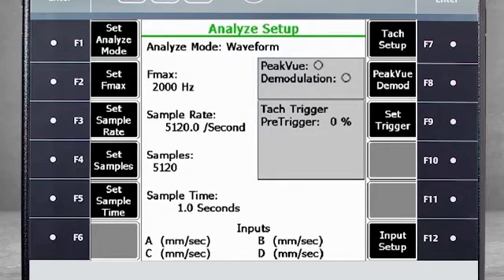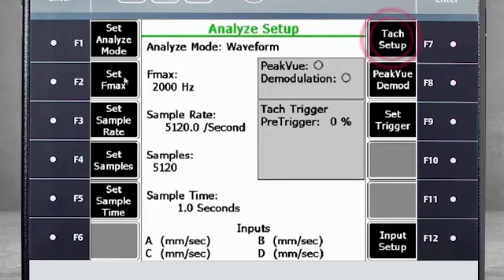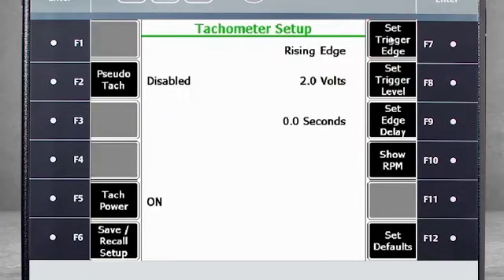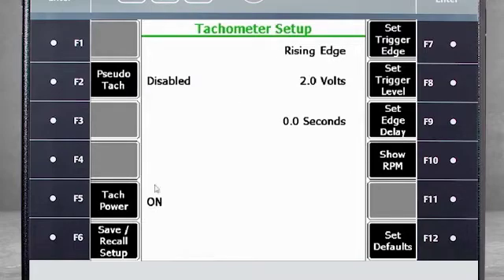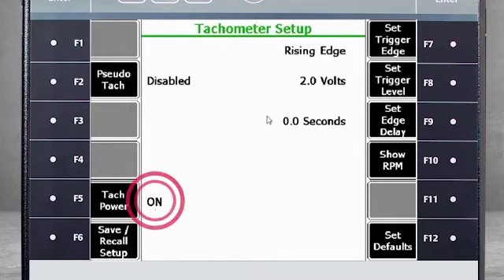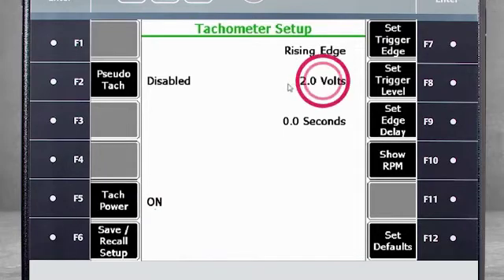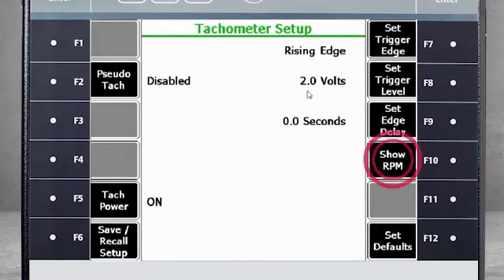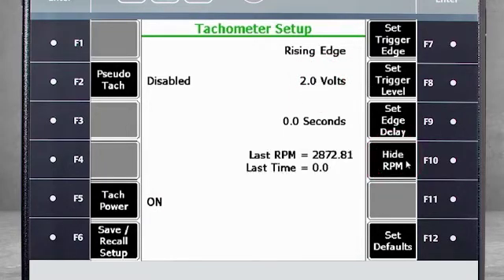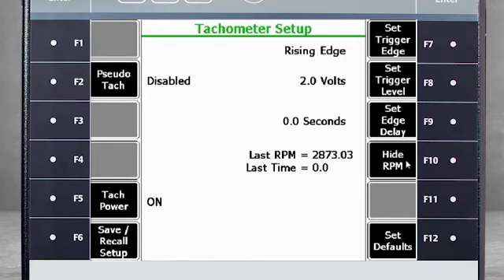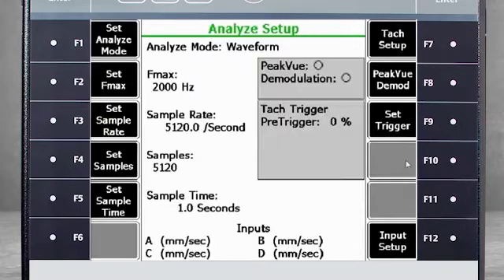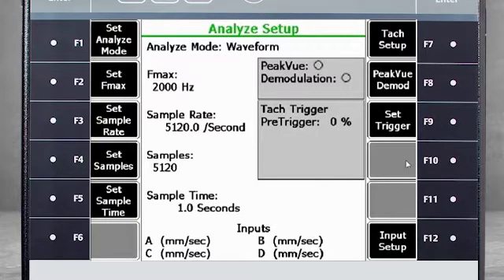If you have a tach sensor installed, you can use F7 to configure it and collect speed data. For this tutorial, I am using a traditional photo tach, so the power is on. My trigger level will be 2 volts. Select F10 Show RPM to confirm it is working. Since I now see speed data on the screen, I know it is working.